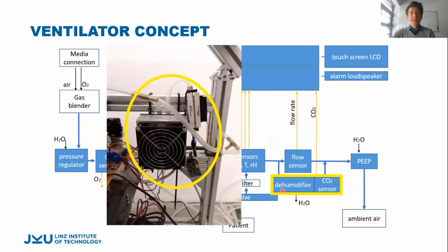Here is a dehumidifier and a CO2 sensor. The CO2 sensor is an optical sensor working on the principle of non-dispersive infrared. Being optical, it's very prone to errors from condensation, so we need a dehumidifier to remove the humidity and condense it. There's a Peltier cooler here, and then the cold air comes out and is heated again so the relative humidity sinks below 100%. Then it goes to the CO2 sensor.